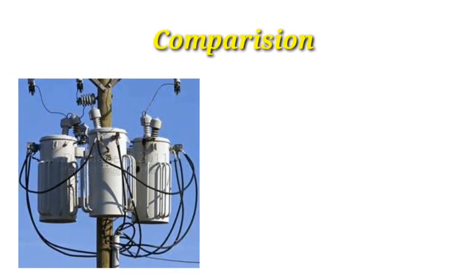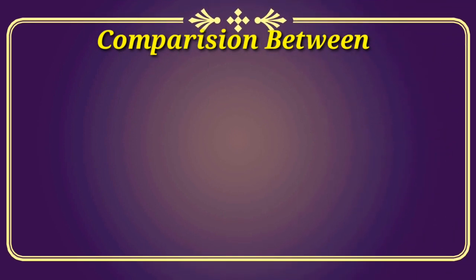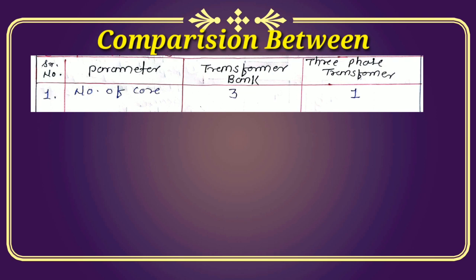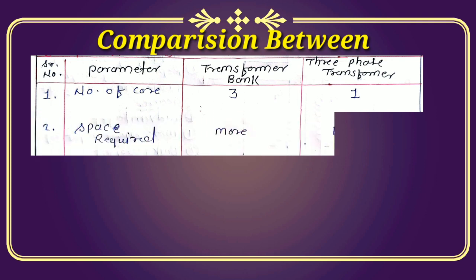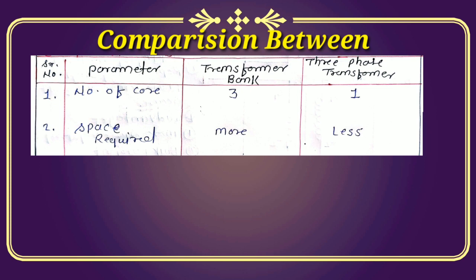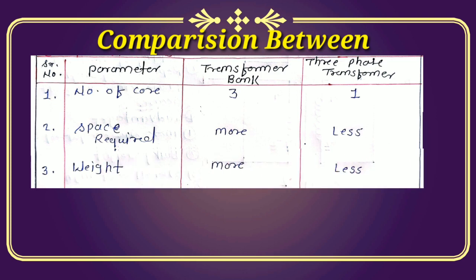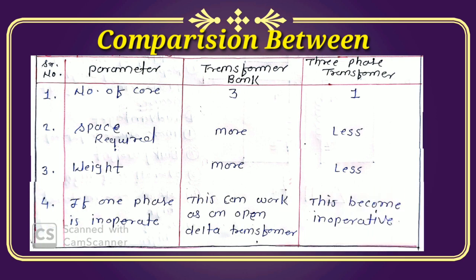Now let's compare the transformer bank and the three-phase transformer. First point — number of cores: in a transformer bank we use three cores, while in a three-phase transformer we use only one core. Second — space required: the transformer bank requires more space, while the single unit transformer requires less space. Third — weight: the bank has more overall weight compared to the single unit three-phase transformer. Fourth — if one phase is inoperable: the transformer bank can still work as an open-delta transformer, but the single unit three-phase transformer becomes completely inoperable.